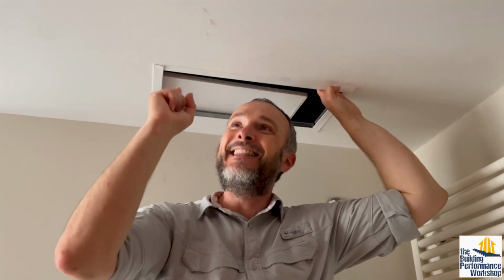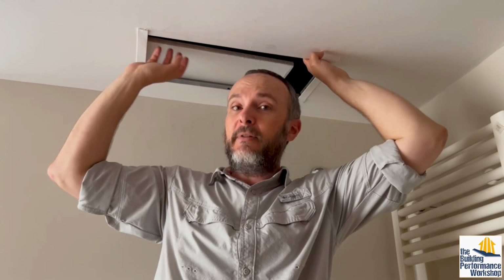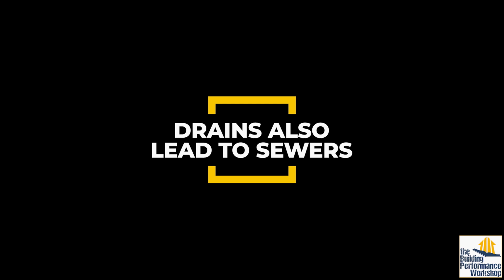So there needs to be another access hatch, a big one like we had in the other room, to be able to get in and clean this coil, because this unit is especially the kind of unit that you are going to want to clean that coil because of the filtration and the return to plenum setup here, this ceiling plenum.